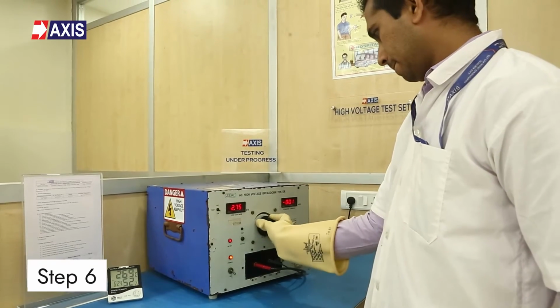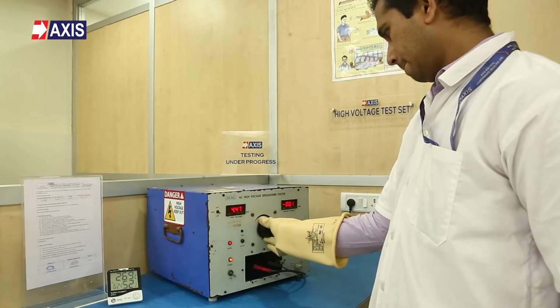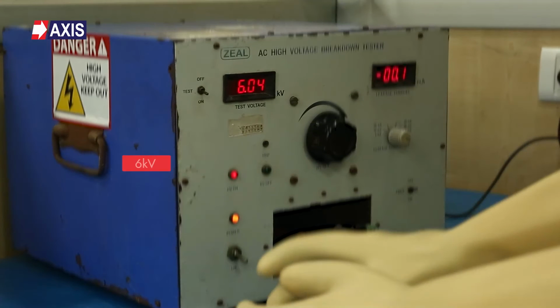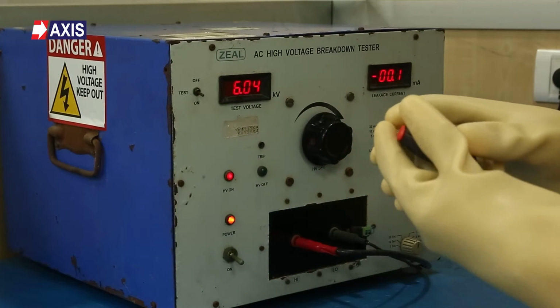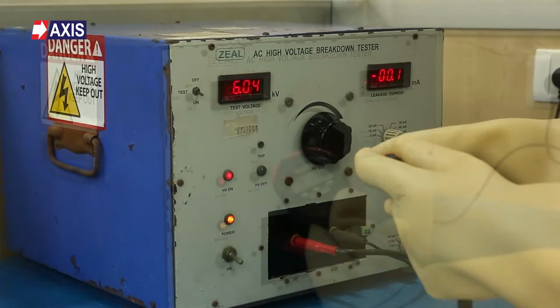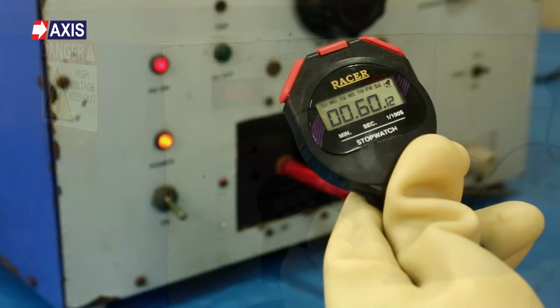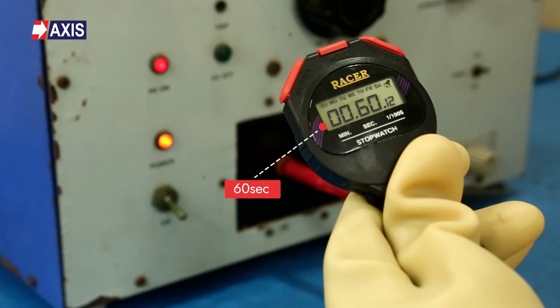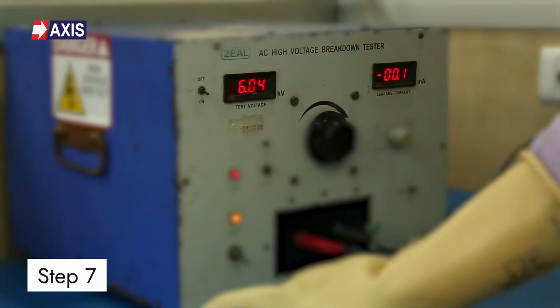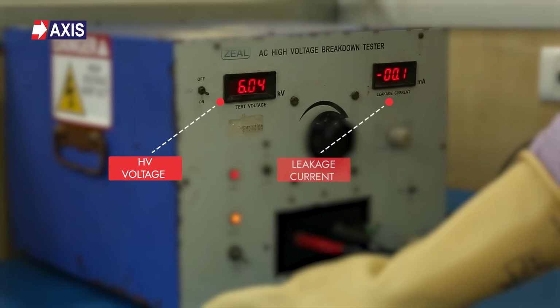Step 6. Rotate the HV knob gradually to get the desired high voltage value, that is 6 kV. Once the voltage reaches the desired value, start the stopwatch to test the sample for the required duration, that is 60 seconds. Step 7. Observe the high voltage and leakage current on the HV tester.